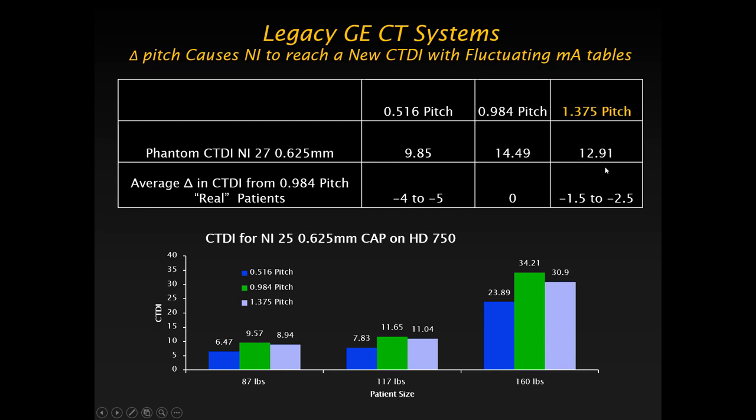And so this shows that there's a huge dose reduction just by using a pitch of 0.5 or 1.4. The problem with using a pitch of 0.5 was that this tends to give you artifact if your patients are moving or if they're breathing: pediatrics, Parkinson's, mentally delayed patients. They don't respond well to these ultra slow scan times where you're taking a picture in that same area twice with a redundant pitch.